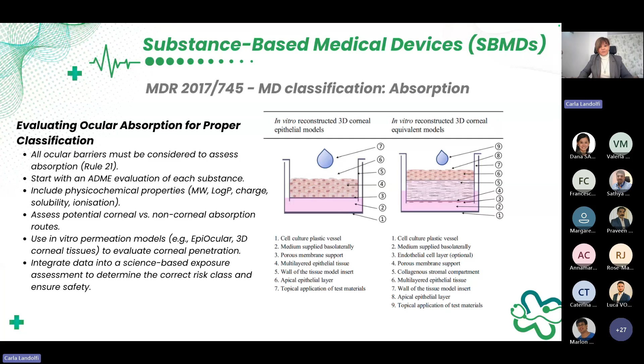And the reverse is also true. Relying only on corneal permeation tests is not sufficient without ADME data and a proper chemical-physical evaluation. The results remain incomplete and are not adequate for a correct risk assessment or for supporting the appropriate MDR classification. We have direct experience with these. Notified bodies have explicitly asked for and endorsed this integrated approach, confirming that only the combination of ADME, chemical characterization and permeation studies provides the level of evidence required under the MDR.